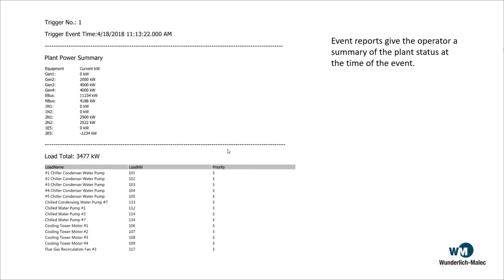So this report shows what was currently running in the plant as far as generators and utility coming into it. Down below, it shows what was selected to be load shed, that total load of 3,477. And on the next screen, it shows what was actually shed. So that's just an indication of the actual relays that were fired and tripped those loads. Now, one thing I want to talk about, the way we maintain this, you can imagine that you need to shed very quickly. So in the background in our control system, we're constantly calculating what needs to be shed, and we're sending, to get a little technical, a bit stream of zeros and ones of the outputs that need to be fired all the time. So when we actually see that trigger, like the utility breaker opens, those zeros and ones immediately get moved over to fire those relays, and the shed event happens.